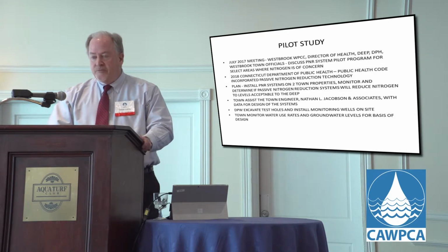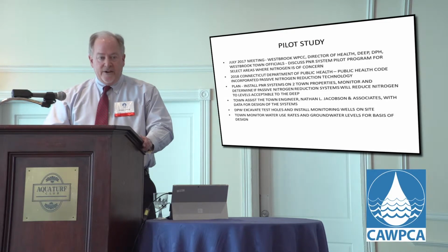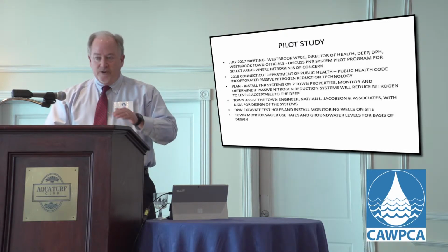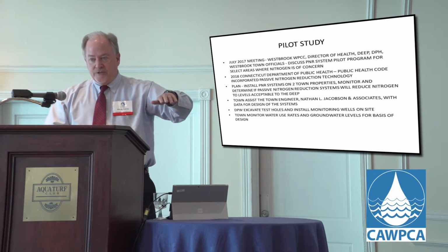As you know from the municipal treatment plants, you have an aerobic phase where you nitrify the ammonia to create nitrites and nitrates, but then you require an anoxic phase, with the carbon source present, for denitrification. So that's the concept behind this system: you create a layered approach where it nitrifies through an upper sand layer.